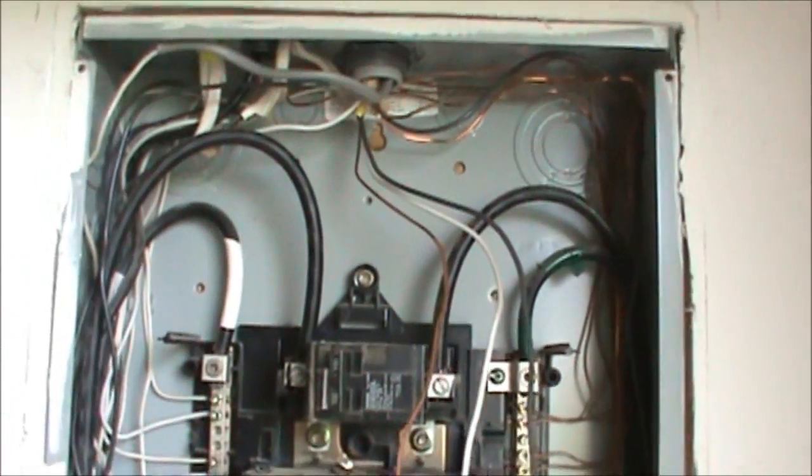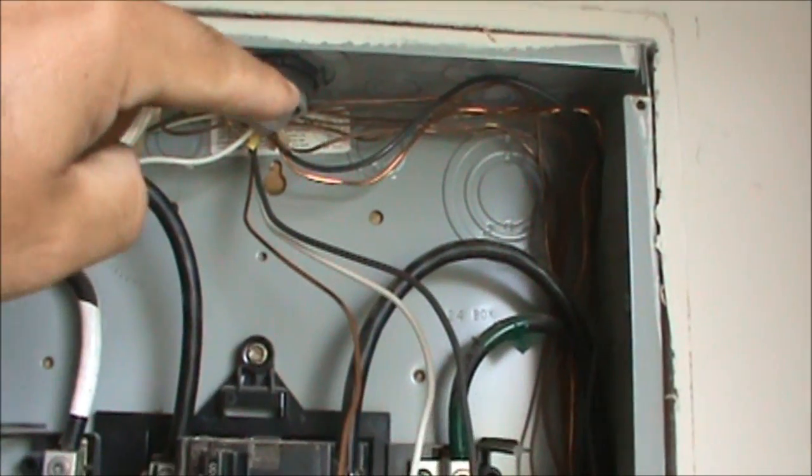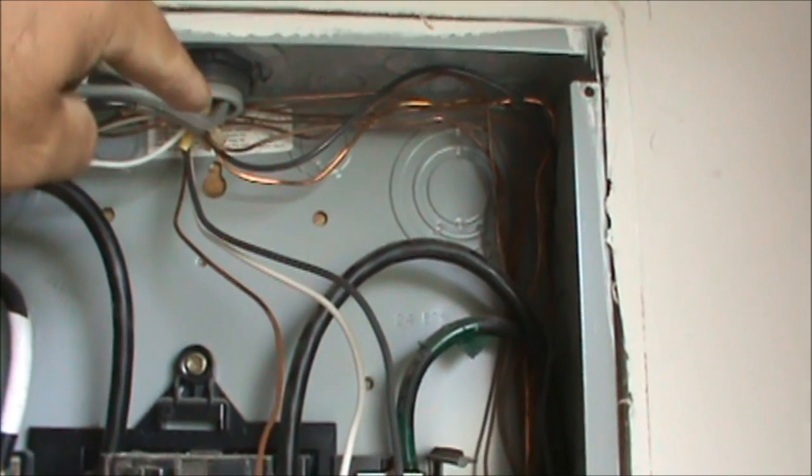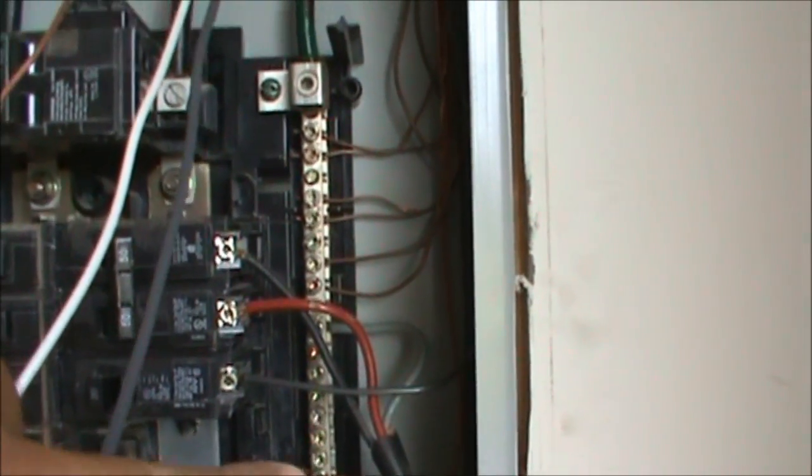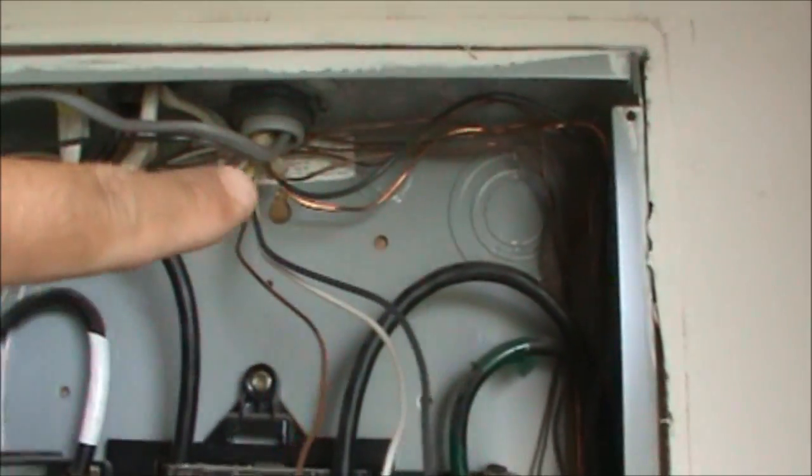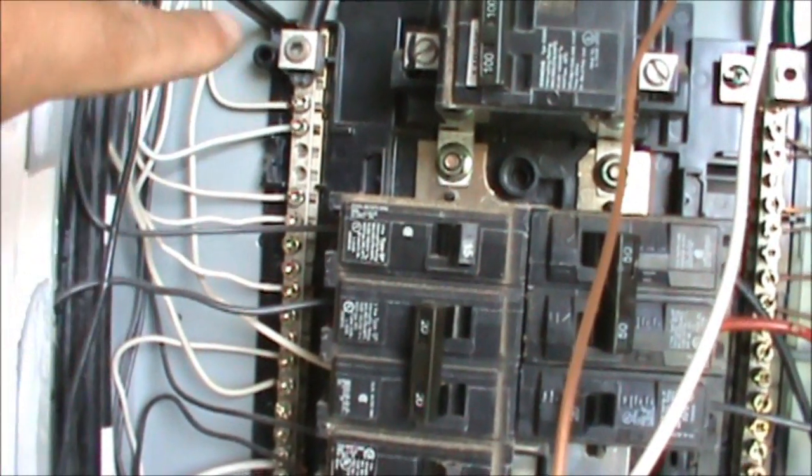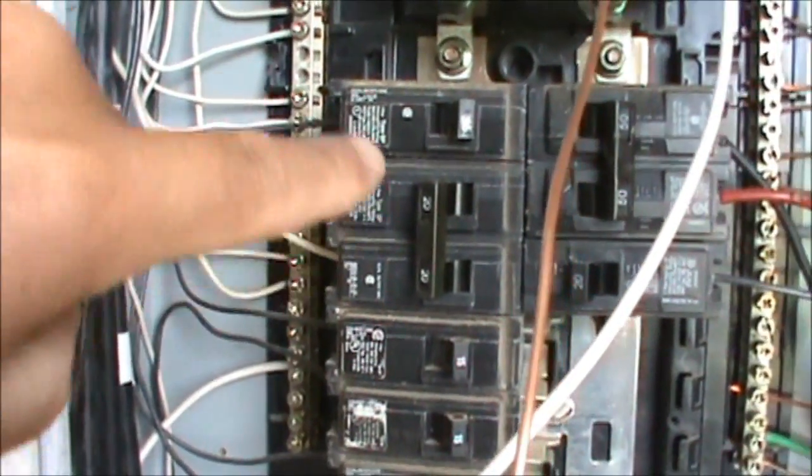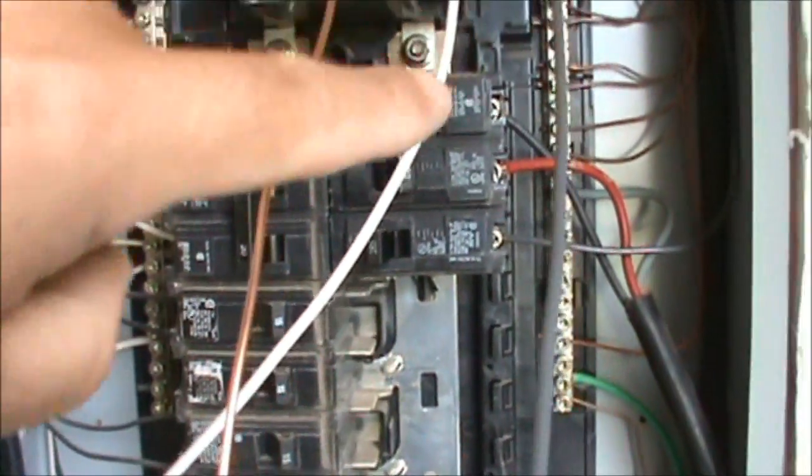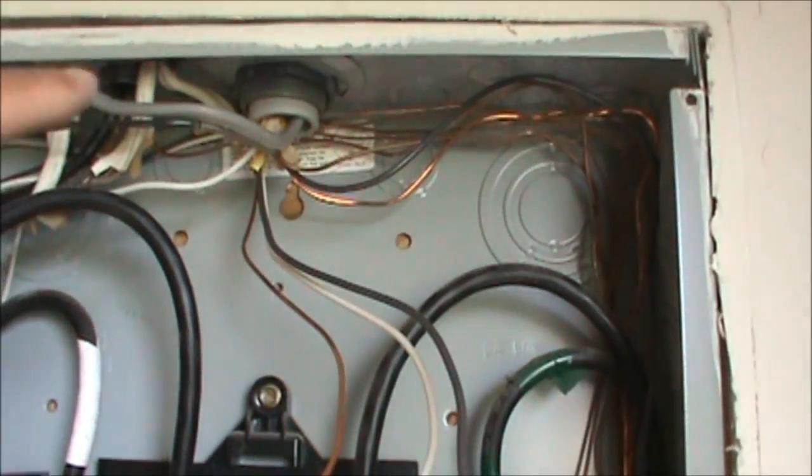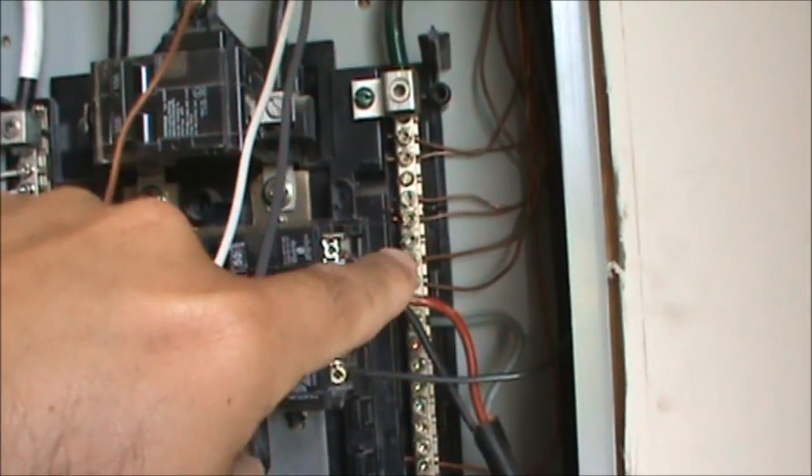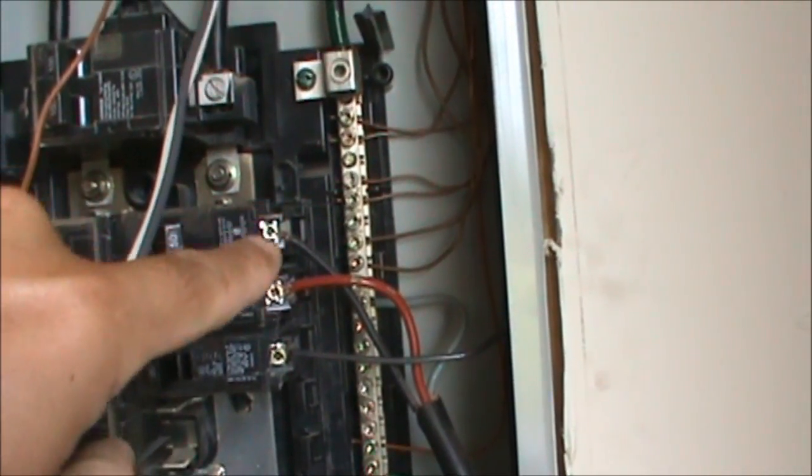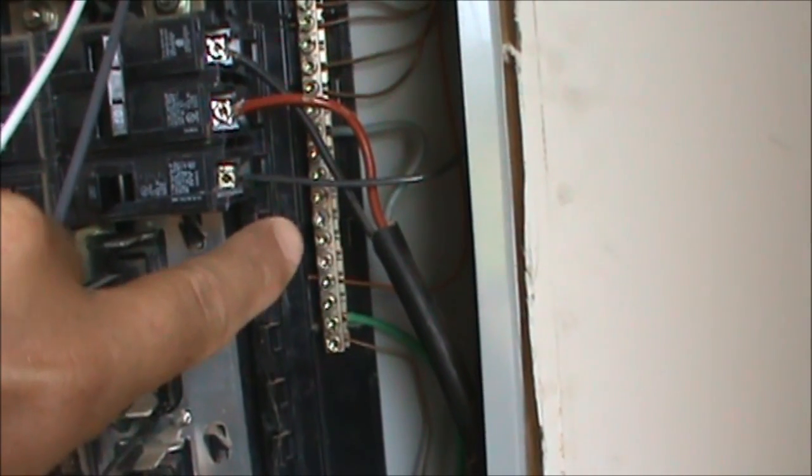If we take a look in the panel, you can see in my particular panel all the ground wires are going out to the right, they're coming down and they're hooking on to that silver bar right there. And if we go up top and look over, you'll notice that all the common wires, all the white wires, are going over here to this bar. And the black wires generally are going to the breakers. You want to try and keep your panel nice and neat so if you're ever working with electricity you know what you're doing. So what we're going to be doing is we're going to run our ground from the top all the way down and tie it in to the bus bar to an empty screw.